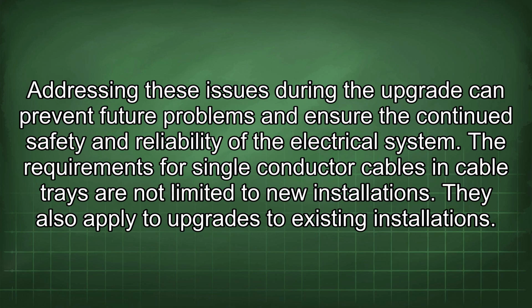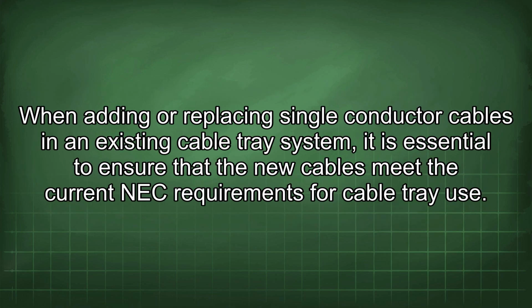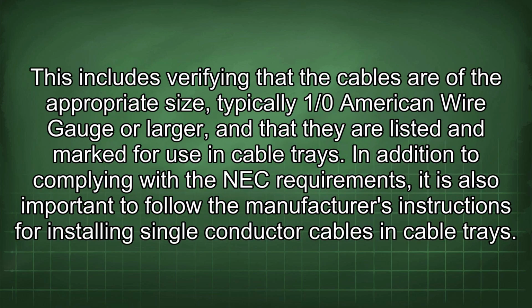The requirements for single conductor cables in cable trays are not limited to new installations. They also apply to upgrades to existing installations. When adding or replacing single conductor cables in an existing cable tray system, it is essential to ensure that the new cables meet the current NEC requirements for cable tray use. This includes verifying that the cables are of the appropriate size, typically 1/0 American wire gauge or larger, and that they are listed and marked for use in cable trays.